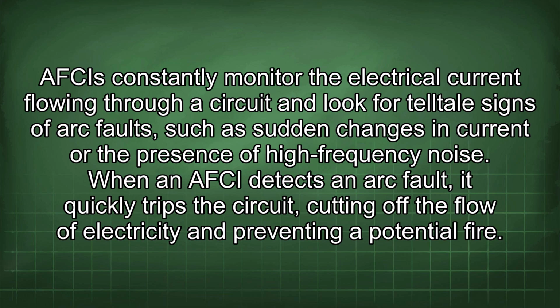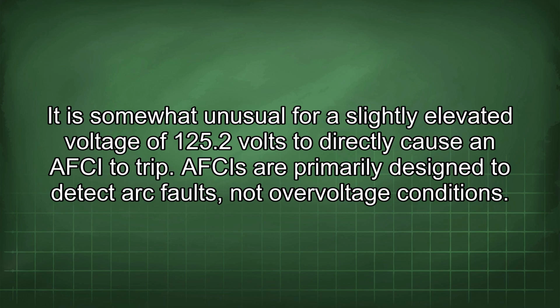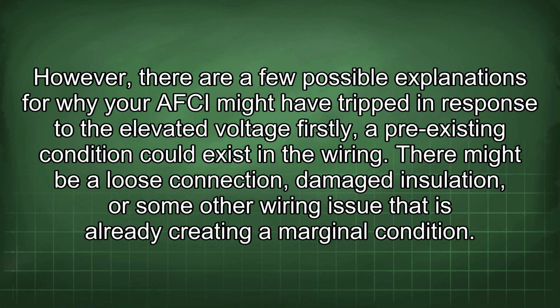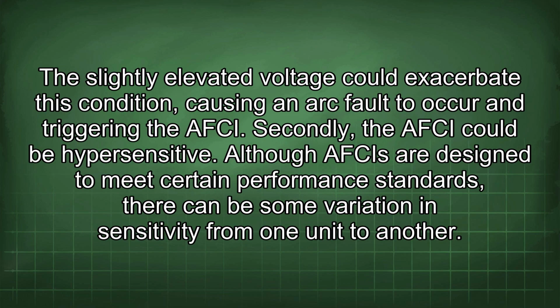a potential fire. It is somewhat unusual for a slightly elevated voltage of 125.2 volts to directly cause an AFCI to trip. AFCIs are primarily designed to detect arc faults, not over-voltage conditions. However, there are a few possible explanations for why your AFCI might have tripped in response to the elevated voltage. Firstly, a pre-existing condition could exist in the wiring. There might be a loose connection, damaged insulation, or some other wiring issue that is already creating a marginal condition. The slightly elevated voltage could exacerbate this condition, causing an arc fault to occur and triggering the AFCI.